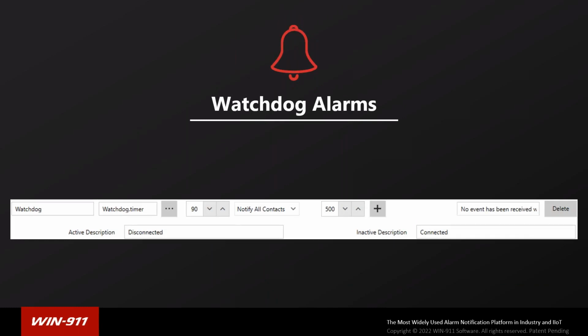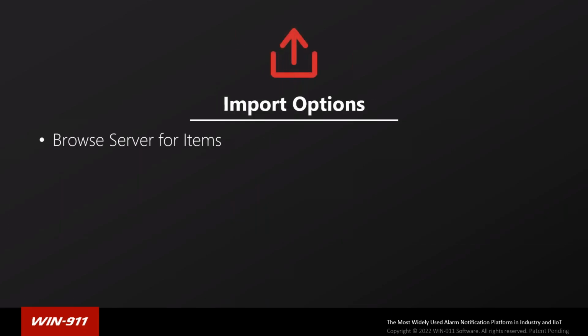Watchdog alarms are alarms where we watch a particular tag value, and if it doesn't update within the time interval, which I realize I cut the headers off of, but the timeout period is right there, 90 seconds. So if you don't see an update within that timer, then this alarm becomes active. It's a good way to monitor a PLC or your connection if you're using OPC. It'll tell you whether or not you have disconnected. Notification policy, priority, the rest of it's pretty much the same. So that's it for the alarm configuration itself.